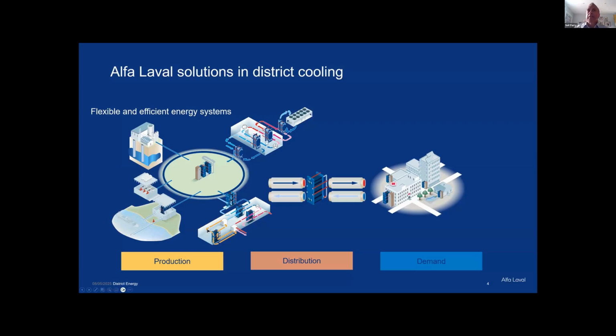So where do we fit in a district cooling project? Well, what you can see here is a very stylized graphic of a district cooling system, and you can see that our products are normally installed anywhere around the sources of cooling, whether that is aquifers, lakes, rivers, etc. Some hydraulic separation required. Also in plant rooms, in chillers, and so on and so forth. Very often also installed as pressure breaks in different places, and then normally in substations at the individual building level. So right across the whole chain from source to use.